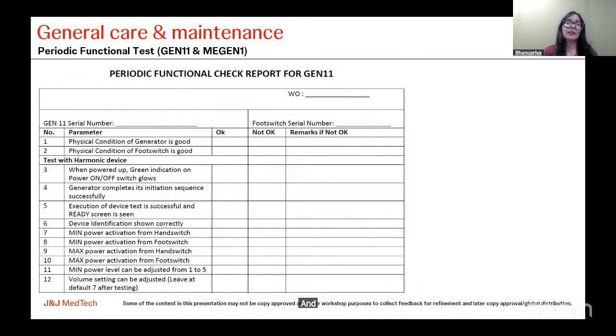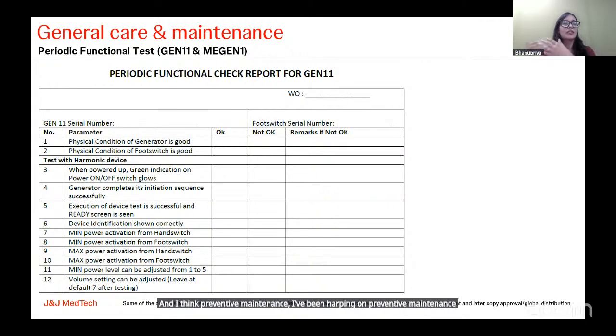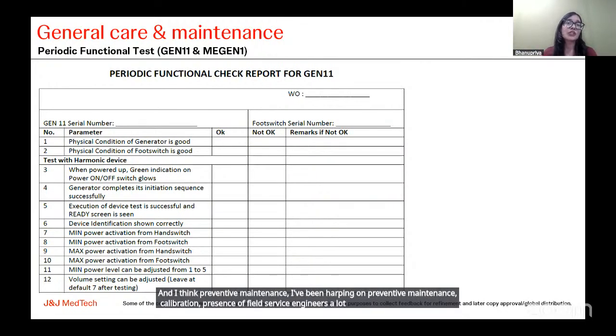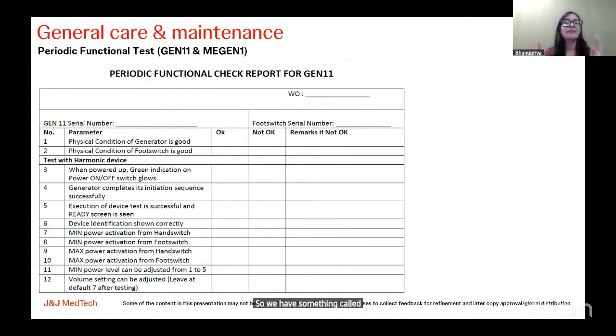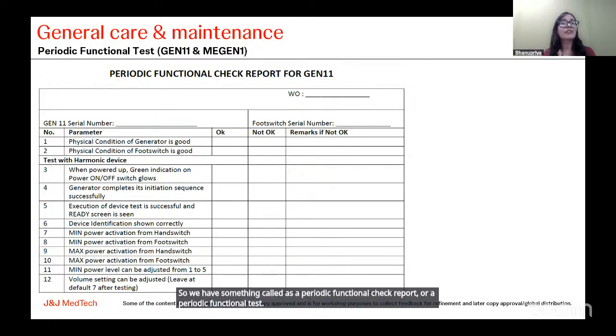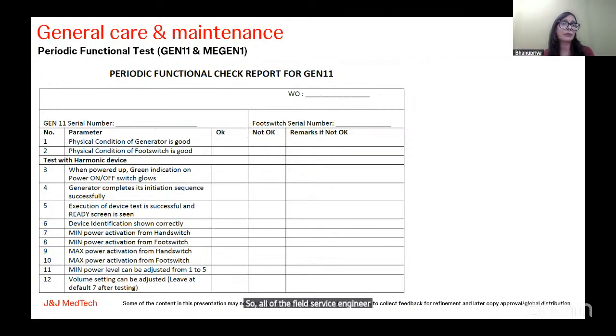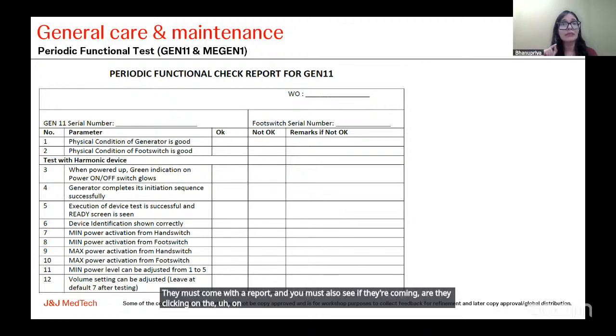And I think preventive maintenance, I've been harping on preventive maintenance, calibration, presence of field service engineers a lot. So we have something called a periodic functional check report, or a periodic functional test. So all of the field service engineers or the sales team, if they come quarterly for a check, they must come with a report, and you must also see if they're ticking the basic parameters which they are required to check on the device.